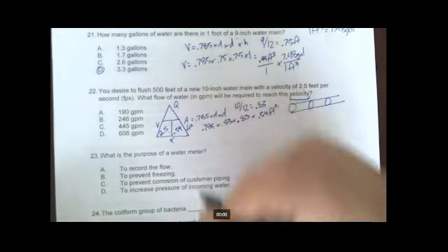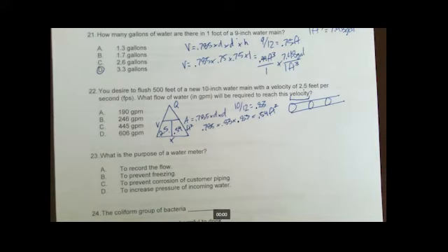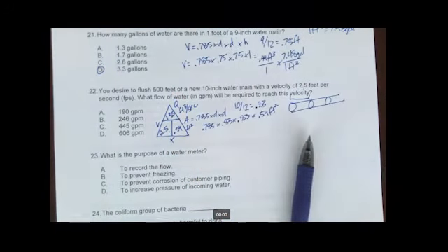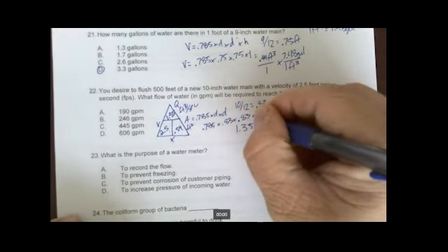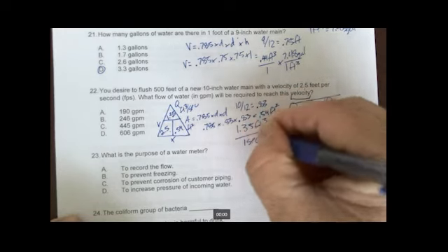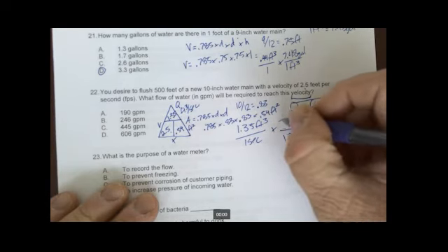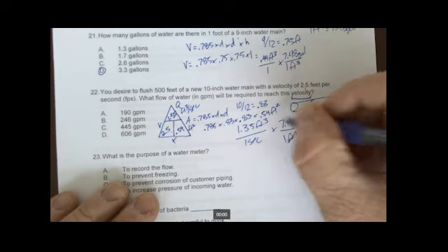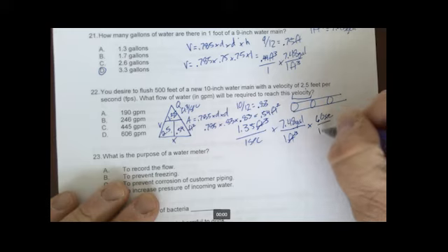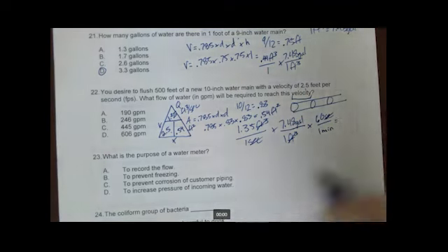When they're across from each other, like I said, you multiply those. So 2.5 times 0.54 is going to give us 1.35. And this will be cubic feet per second. When you solve for Q, Q is always in cubic feet per second. So I need to go over here and convert this 1.35 cubic feet per 1 second. Just like before on the previous one, cubic feet are on top. They've got to be on the bottom to cancel. And I know that there are 7.48 gallons in 1 cubic foot and 60 seconds in 1 minute. The 60 seconds has to be on top, since seconds over here is on the bottom to cancel.